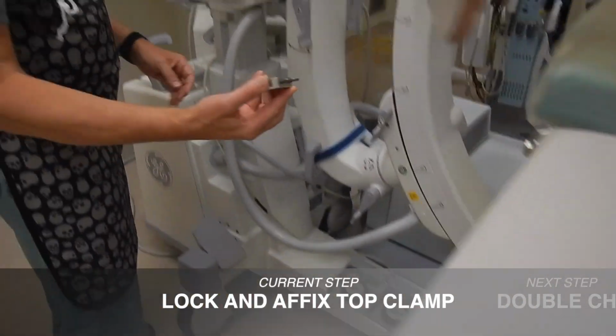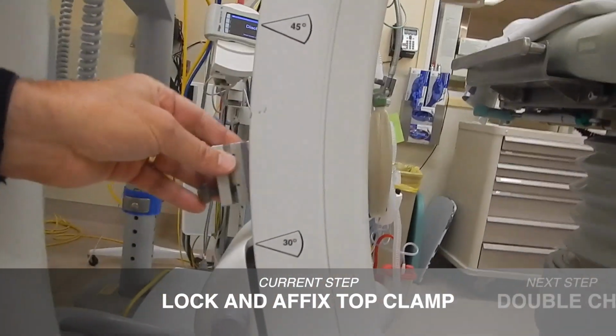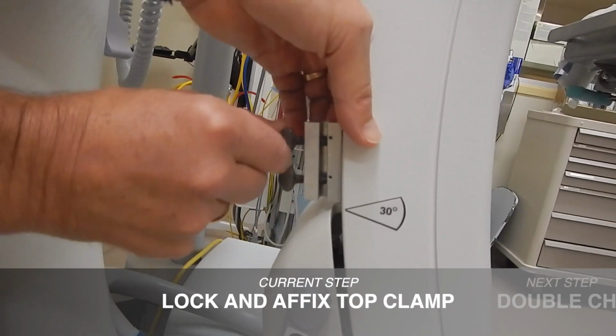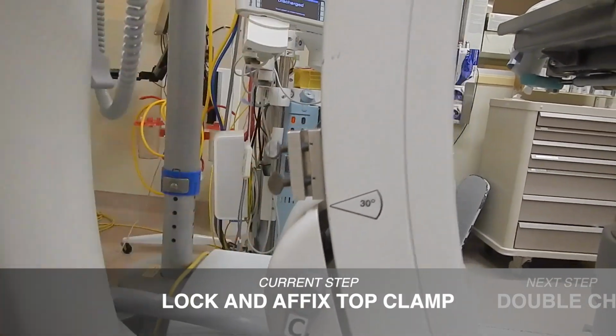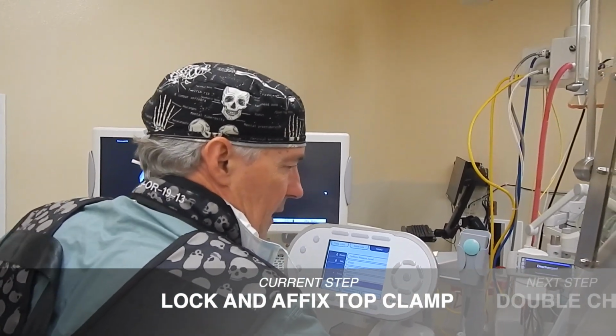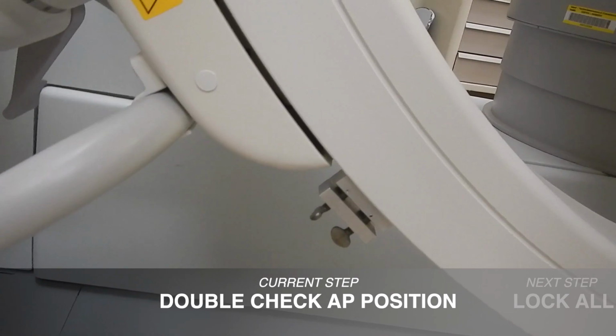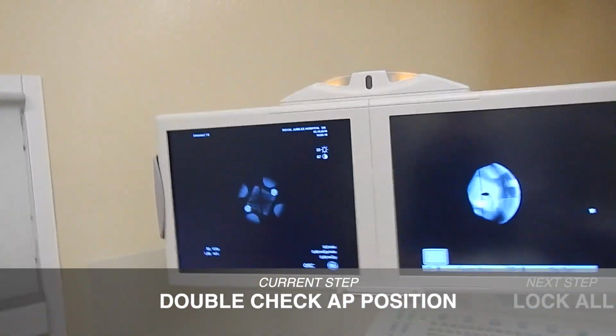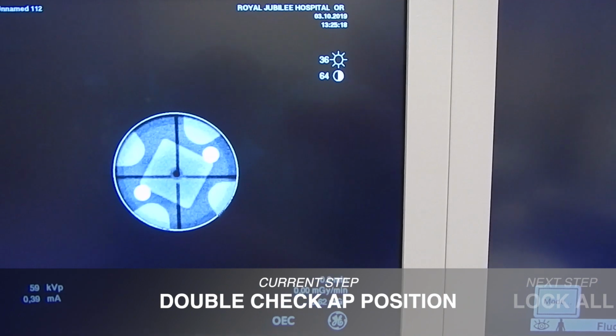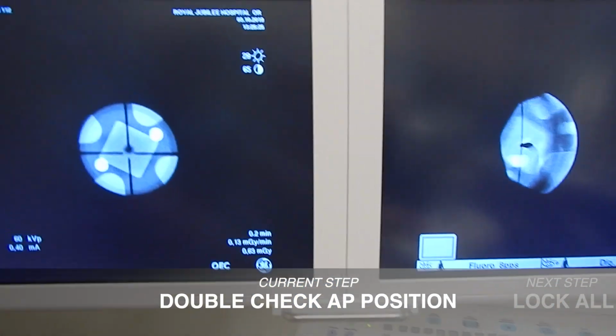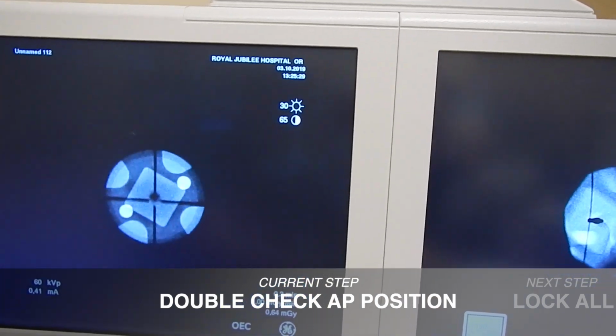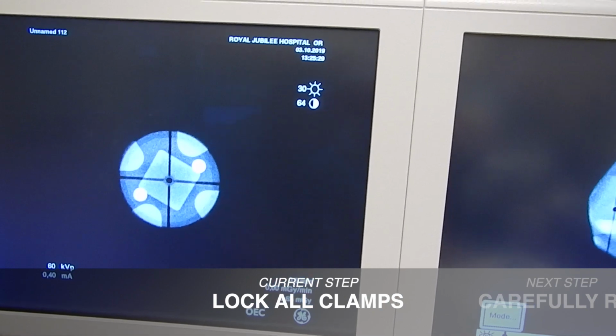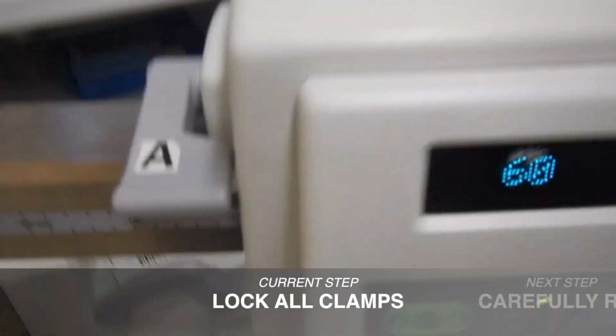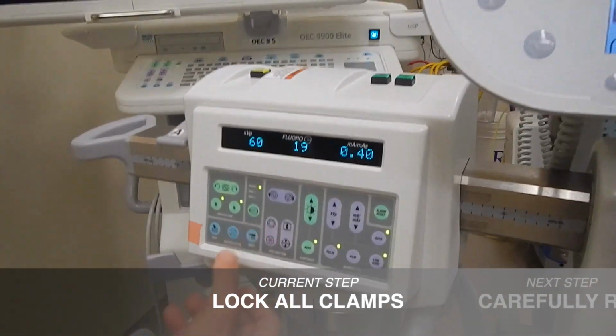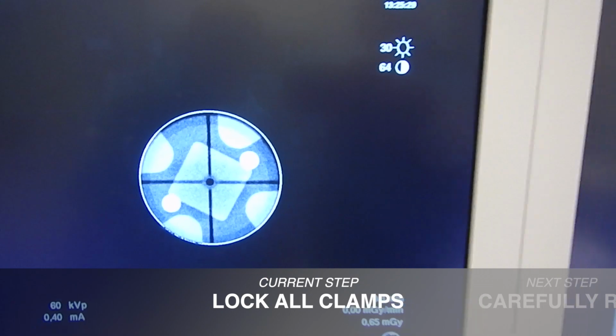And that's your axial calibration position. So before you leave this position, you put this on, and it just slides on like this. You make sure it hits there. Tighten these so they don't come off easily. And then you can go back to your AP position, right up to that lock. Always give it another shot to make sure nothing's changed. And I see a little tiny adjustment needed there and here. Basically, lock A and lock B just fix the vertical and horizontal. So now we have AP calibration and axial.